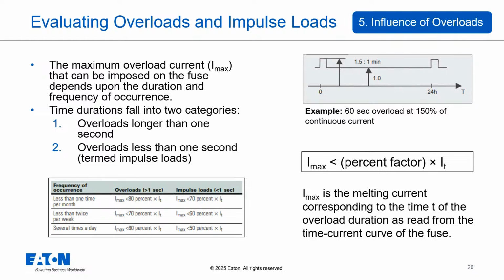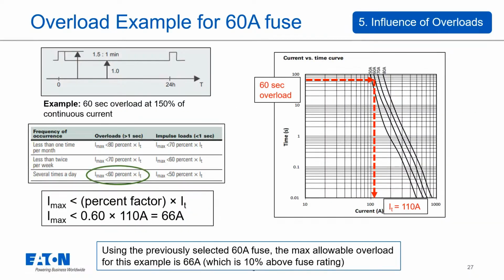Here's a quick example using our previously selected 60 amp fuse. Let's say we need to check if it can withstand a 60-second overload that peaks at 150% of the continuous current. From the time current curve for the 60 amp fuse, we find the melting current IT at the 60-second point. In this example, it's 110 amps. Using a percentage factor of 60% from our table, the maximum allowable overload current, Imax, for 60 seconds is calculated as 0.6 times 110 amps, which is 66 amps. So for a 60 amp fuse, the maximum sustainable overload for 60 seconds is 66 amps. This means the fuse is suitable as long as the actual 60-second overloads in the circuit don't exceed 66 amps.